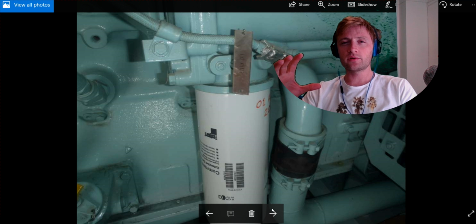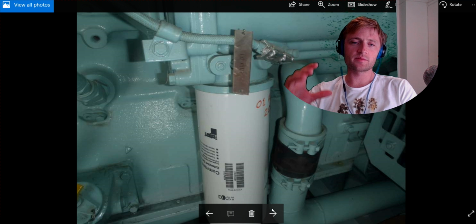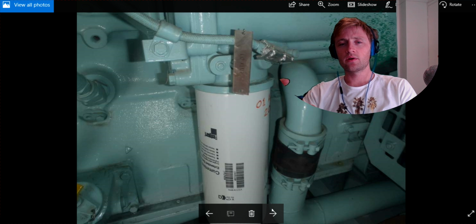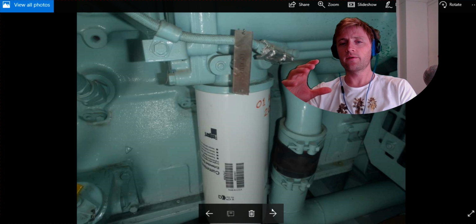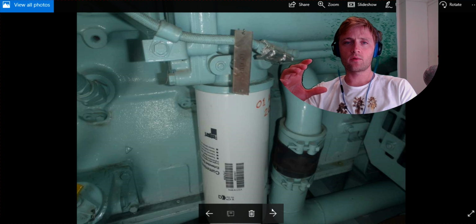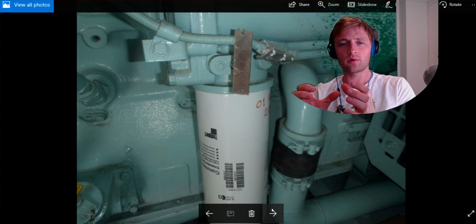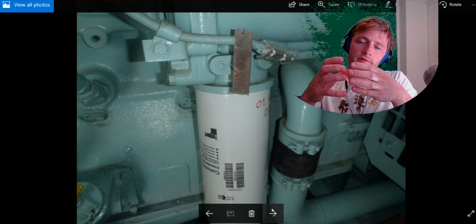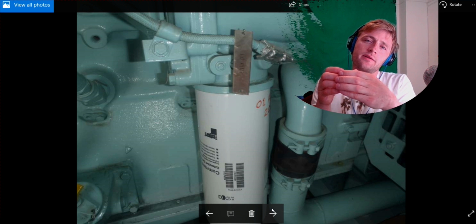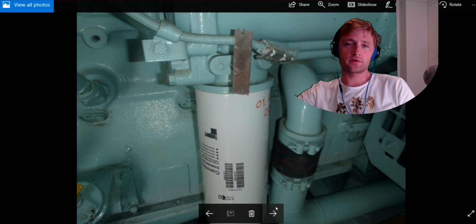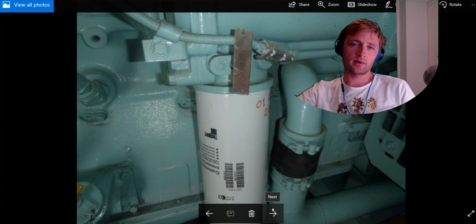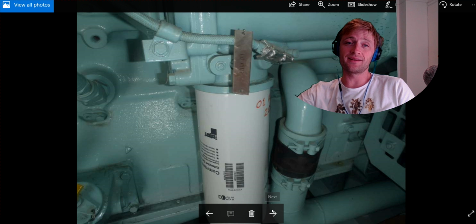Very important information: never overtighten your filters with spanners or special tightening tools. If you see the cartridge on the filter, they are showing how to tighten it. There is about a quarter of a turn, a little bit more, when it's tight. When you feel that the filter is already tight, turn it a little bit so it is only firm. Not overtight, because the other person who will check that and like to change them will be in trouble.